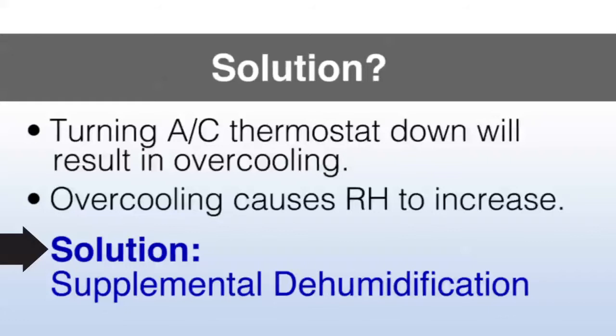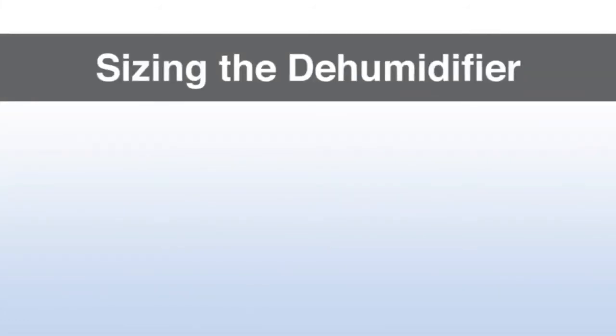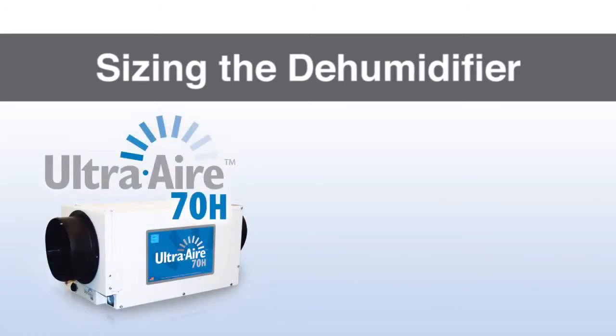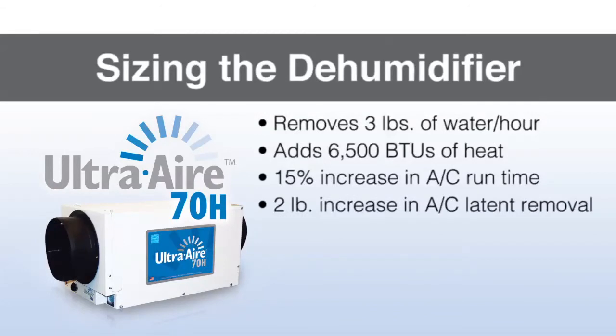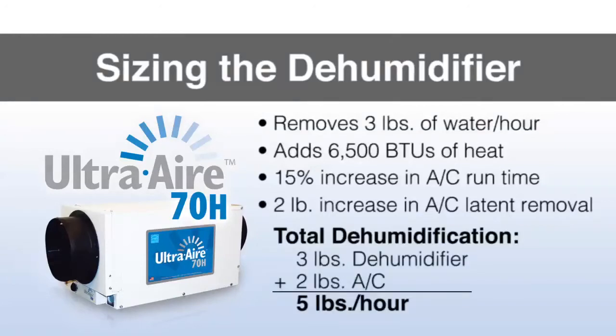The solution would be supplemental dehumidification as needed to remove the remaining 5 pounds per hour. For sizing the dehumidifier, we'd recommend using an Ultra-aire 70, which removes about 3 pounds of water per hour. It adds about 6,500 BTUs of heat to the home, which will increase the AC run time by 15%. Increasing the run time also increases the latent removal of the air conditioner. So adding a little heat, if it is still at the point of doing some cooling, will extend the AC's run time by enough to remove 2 pounds of moisture per hour. The total increase in dehumidification would be 3 pounds from the dehumidifier and 2 pounds from the air conditioner — about 5 pounds per hour — which is going to help significantly with the high moisture level in the home.